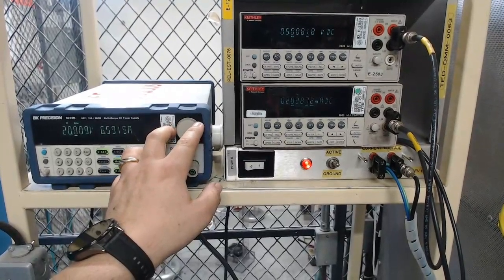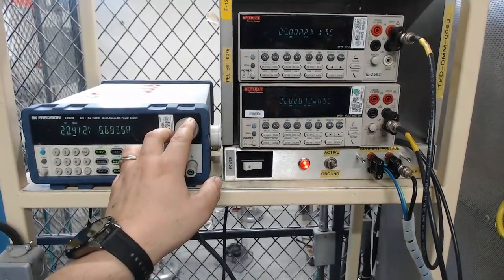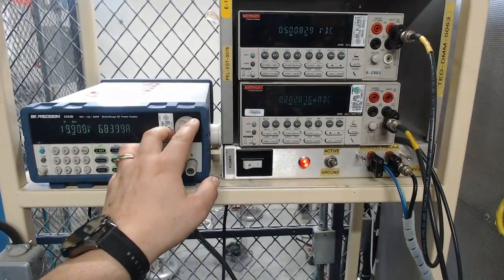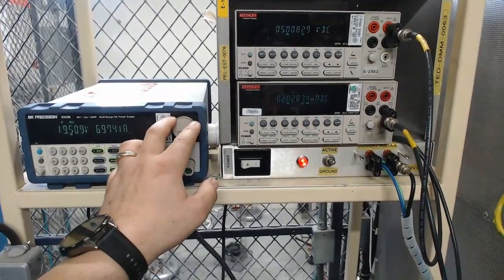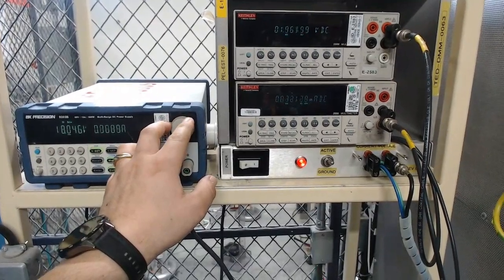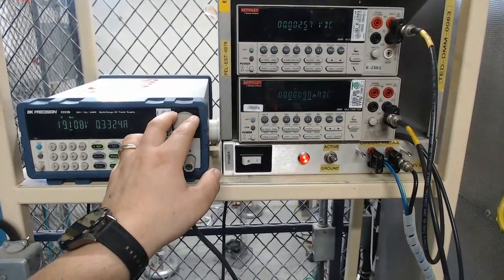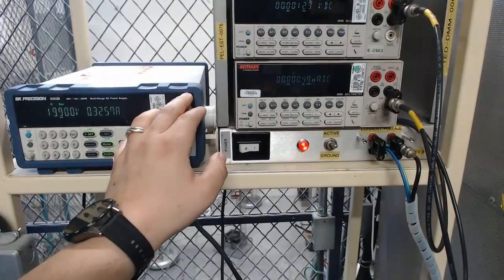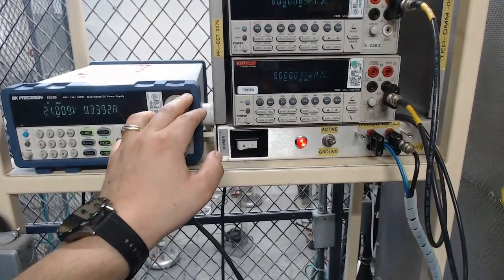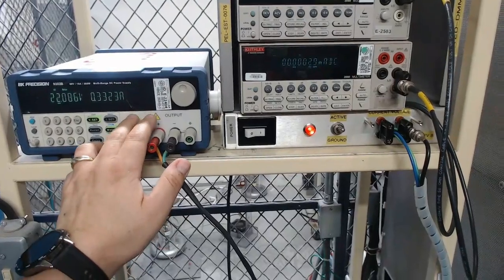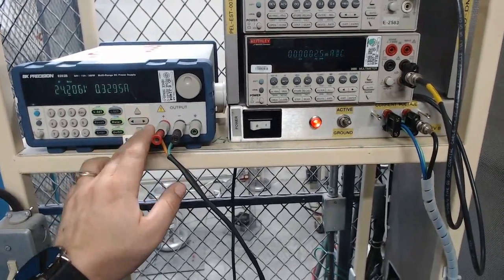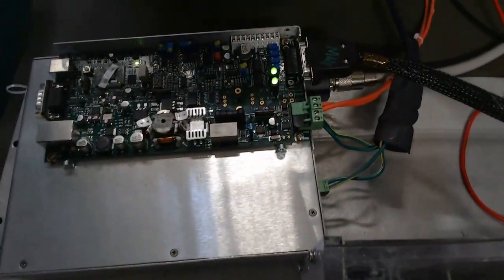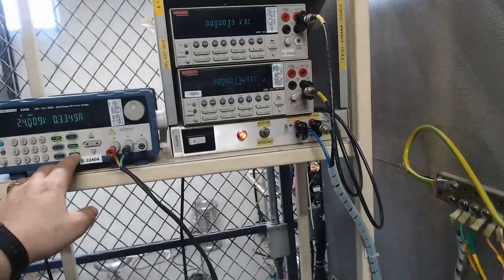As noticed, unit maintains regulation even at lower than 22.7 volts, being able to operate down to the undervoltage fault limit threshold without losing regulation. Since the unit lost regulation at 19.1 volts due to reaching the undervoltage fault, this will be recorded as the dropout voltage. After the fault has been issued, power is recycled to allow the unit to turn on again.